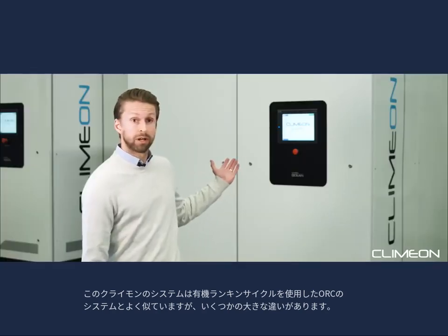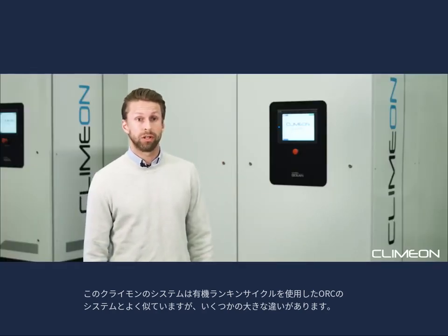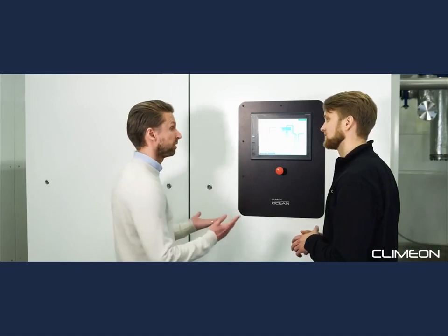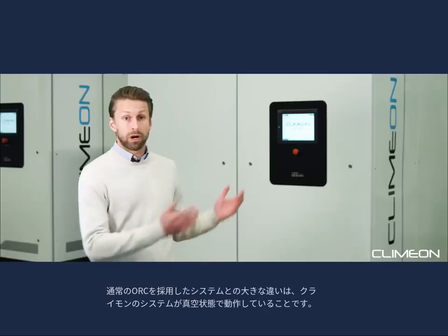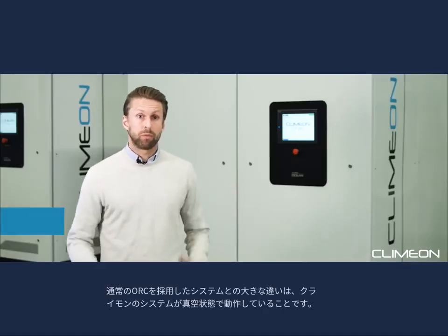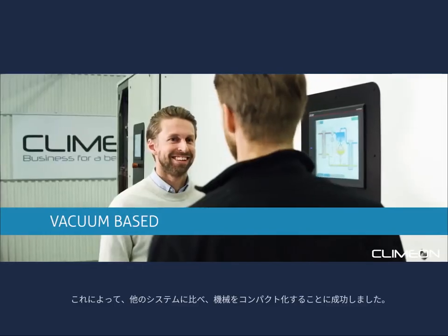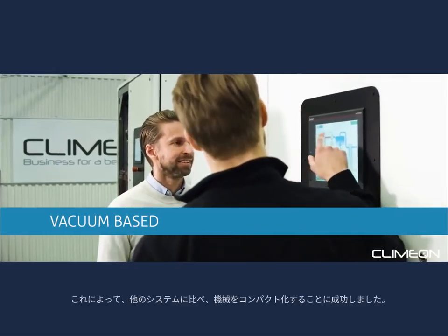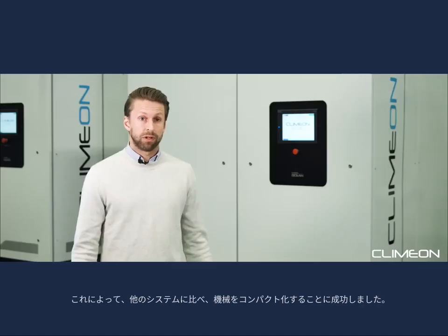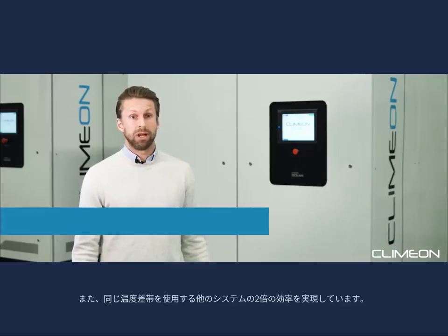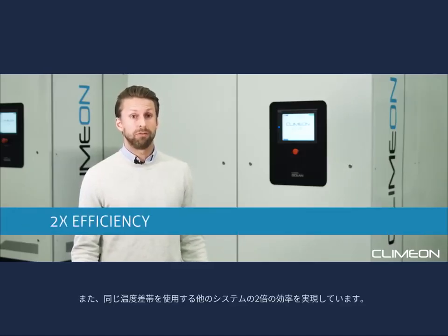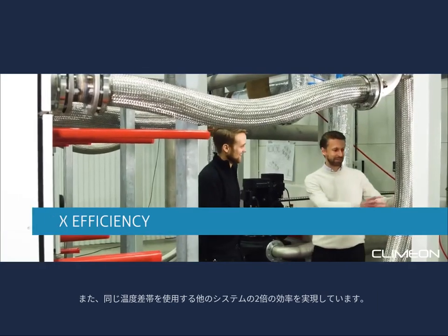This Climeon machine is quite similar to an ORC, but there are some significant differences. One of the main differences between our machine and a normal ORC machine is that we work with vacuum. This means that we can make the machine much more compact than other technologies.